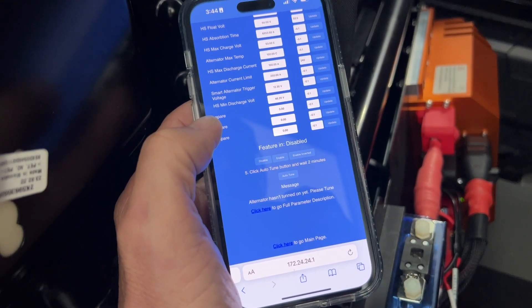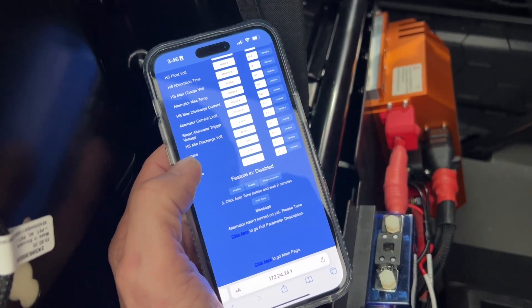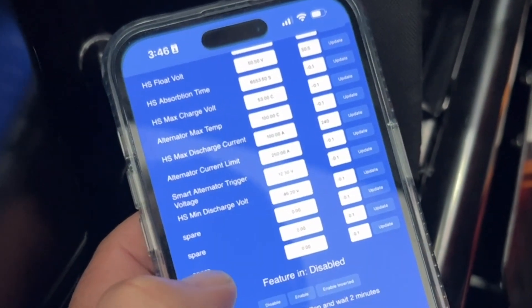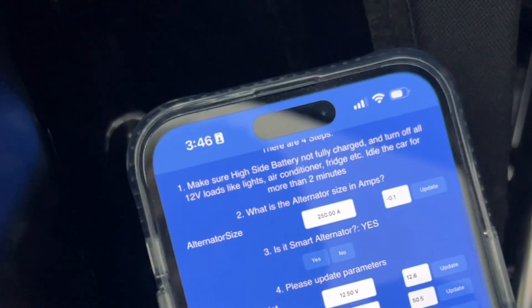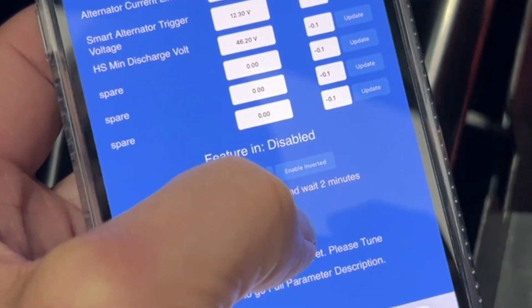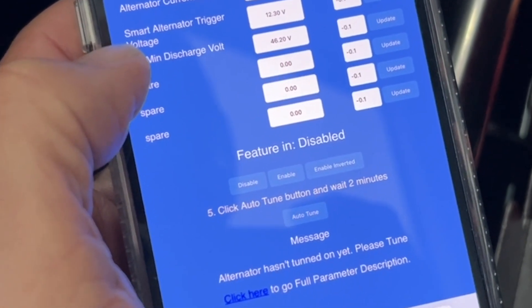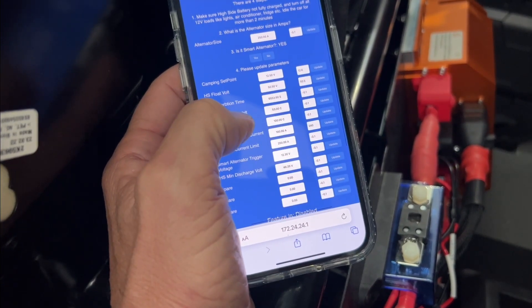Two minutes have passed. You can see the clock at the top of the phone. I check that feature-in is disabled and it's set to smart alternator, which it is in this vehicle — 250 amps — and the other variables are set. Now I hit auto-tuning.